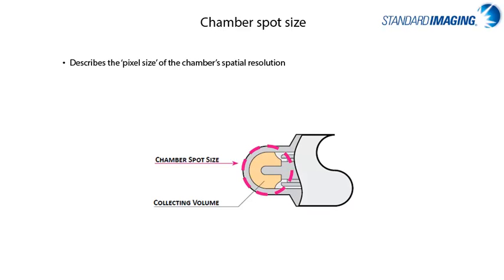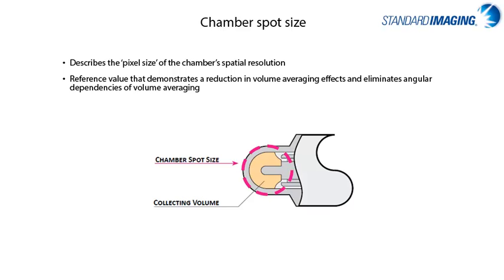Next, I want to talk about a term coined by standard imaging to try and reduce the misuse of the phrase minimum field size when it comes to describing ionization chambers. Standard imaging has recently started using the phrase spot size to describe the effective pixel size of a chamber. This pixel size, or spot size, is a reference value which demonstrates a reduction in volume averaging effects and eliminates angular dependencies of volume averaging.